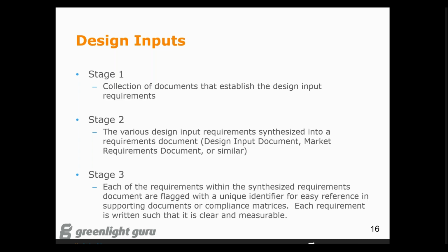Now, in the more developed market requirements documents I've seen, they've started to flag and put some sort of an identifier on each of the specific requirements, such that you could readily demonstrate that you're complying with them, and match them up with any of your validation documents or your design output documents more effectively by flagging them.